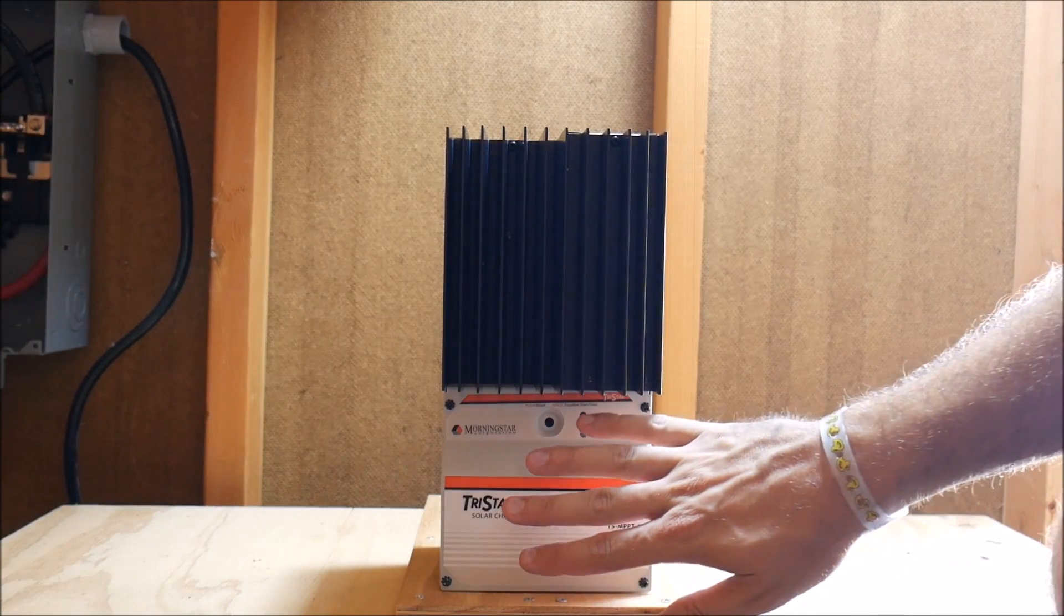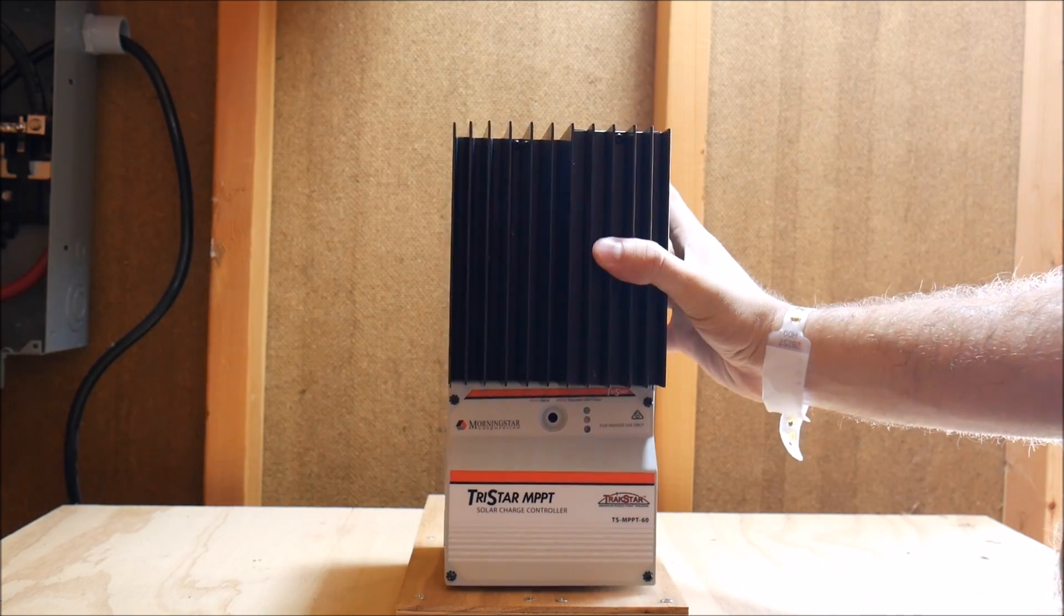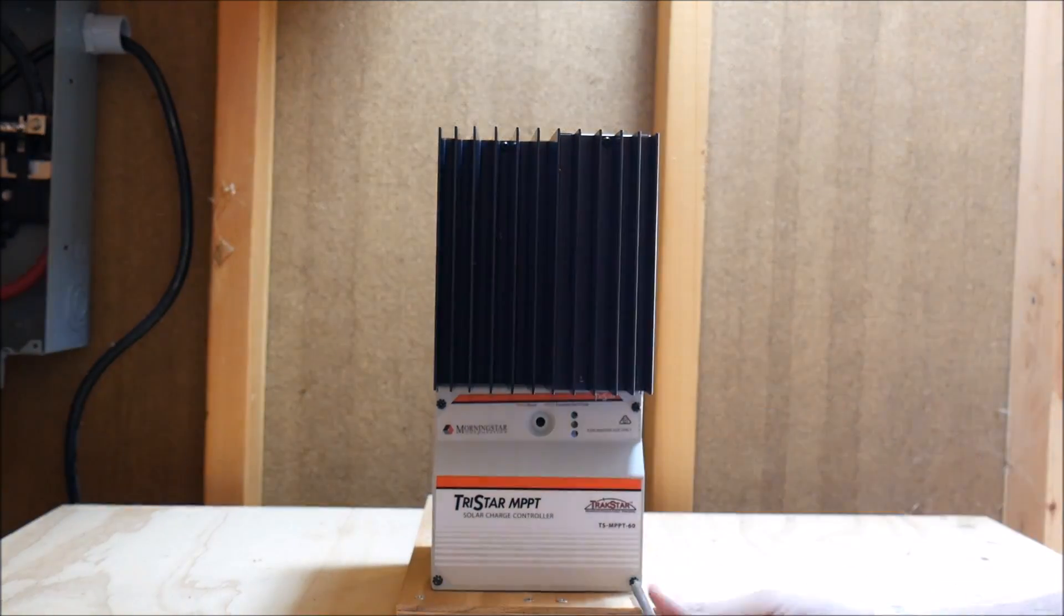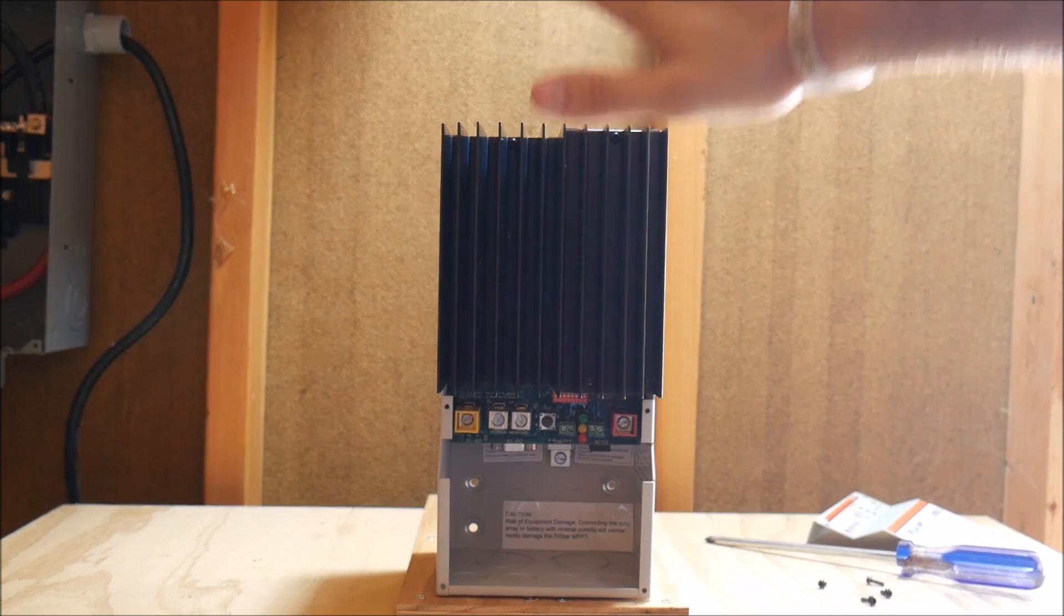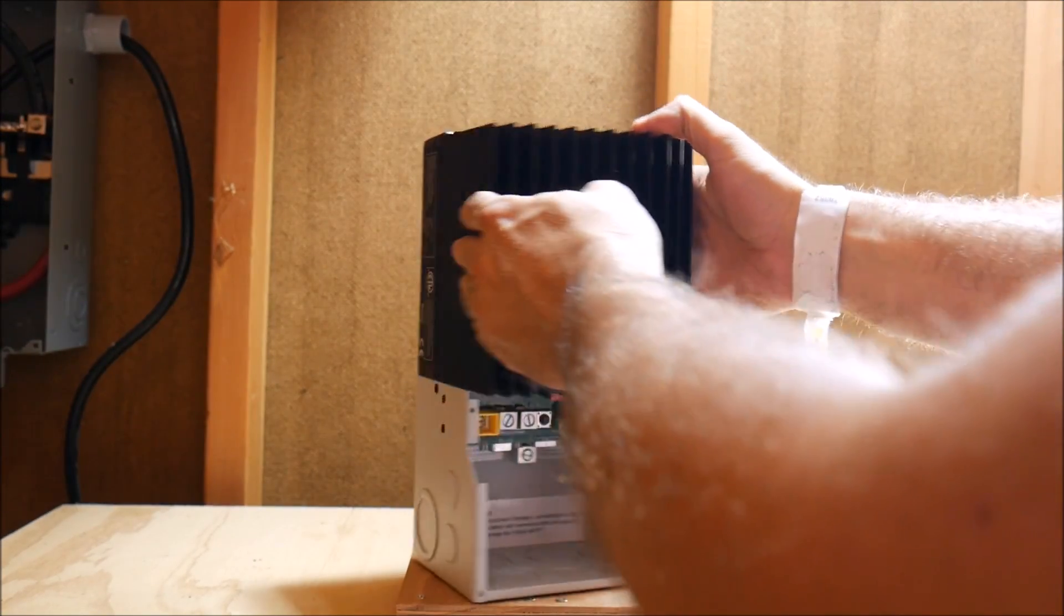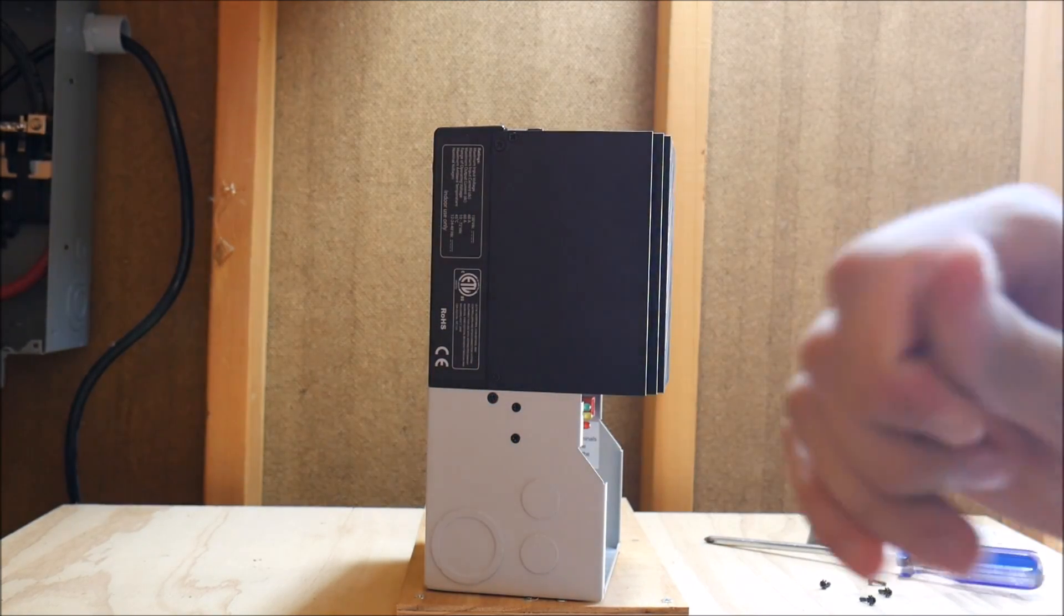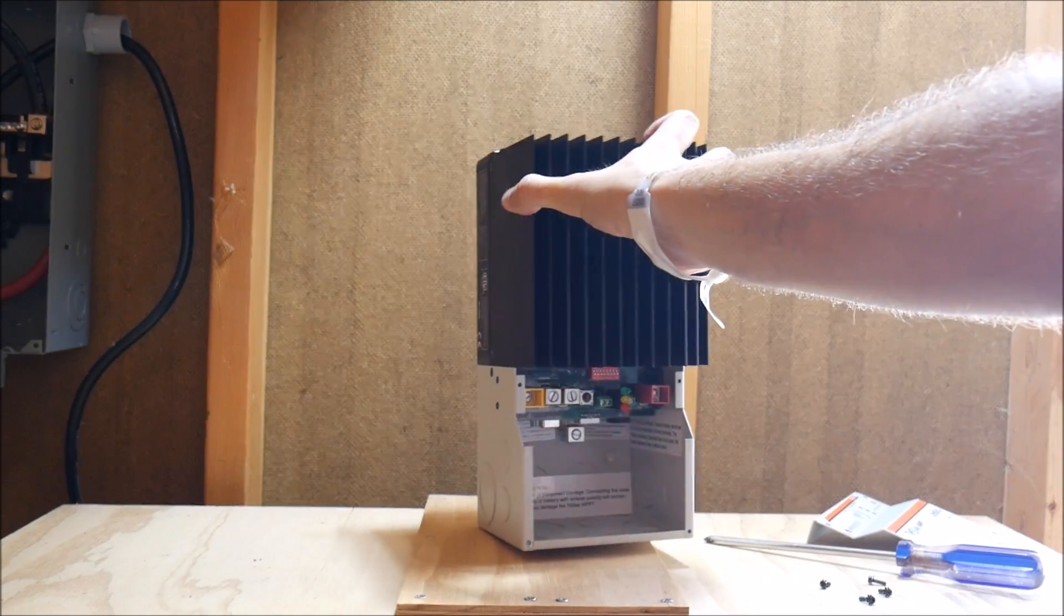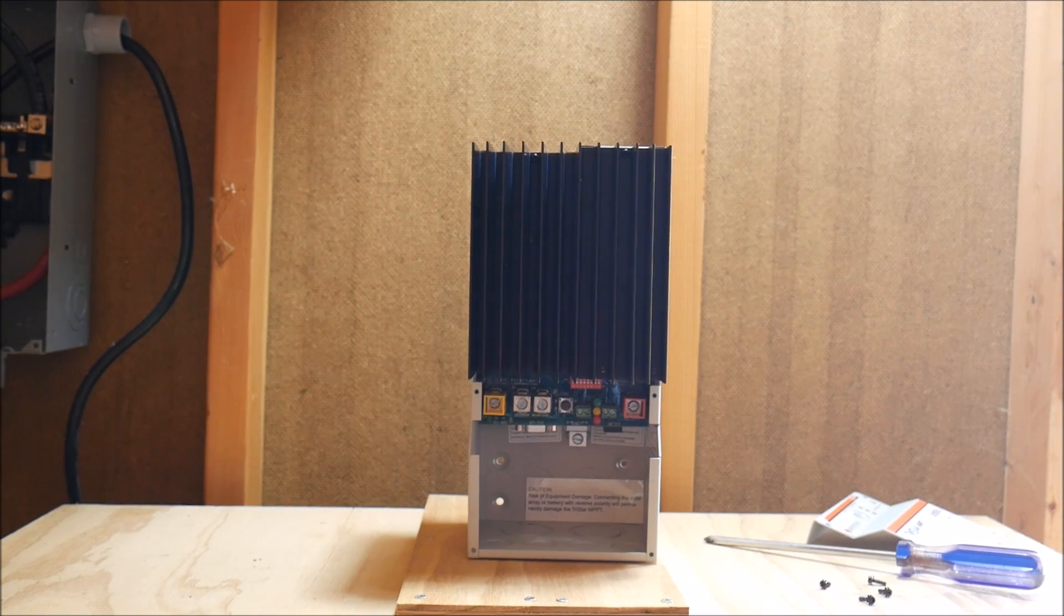The first thing we need to do is remove this panel that allows access to the wire terminals, then remove the knockouts either on the side or bottom depending on how we're going to mount it. I plan on mounting this to a vertical surface, the north wall of the shed, so it'll get the least amount of sunlight. This is a pretty sizable passive heat sink. This thing does not have any active fans, and that's one of the reasons why I like it. This thing can get pretty hot, so we want to keep it in as cool a part of the shed as possible.